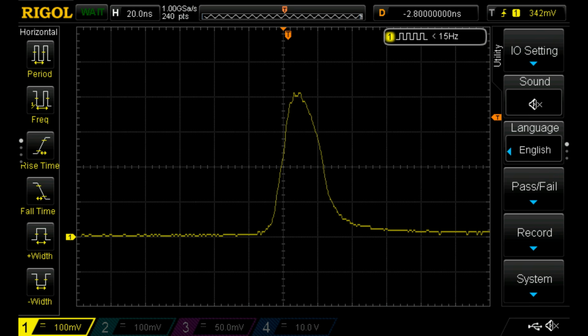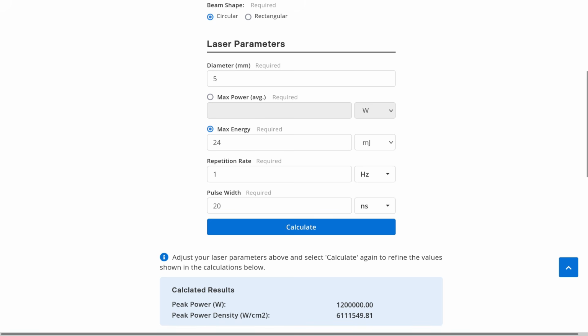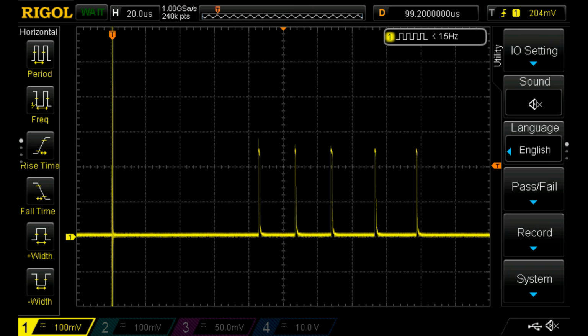I suppose the correct thing to do now would be to take our 120 millijoules and divide it by the number of pulses. This gives us 24 millijoules per subshot, and if we run this through the calculator with a 20 nanosecond pulse width, we end up at a final figure of 1.2 megawatts. Still very, very respectable output. If we reason all this stuff out, we can work out why it is that we're getting 5 short pulses instead of 1 giant pulse.